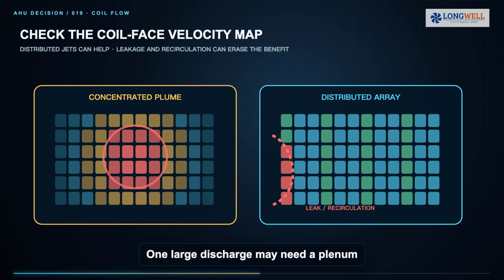Round 4 is what happens across the coil. One large discharge may need a plenum or diffuser to avoid a concentrated velocity pattern. A well-spaced array can divide the flow across more of the coil face. Yet wall leakage, poor inlet clearance, recirculation around a stop cell, or a coil placed too close can destroy that benefit. Check the installed velocity map, do not award the point from geometry alone.